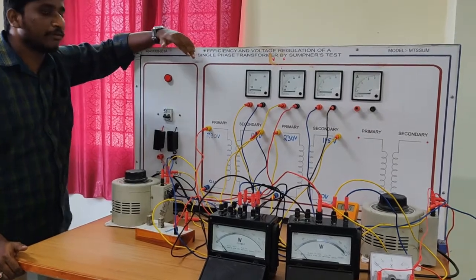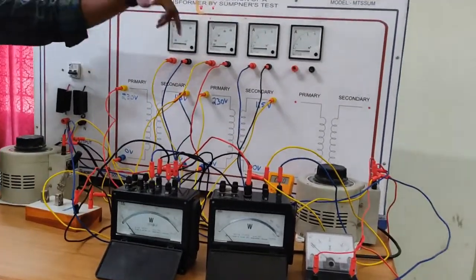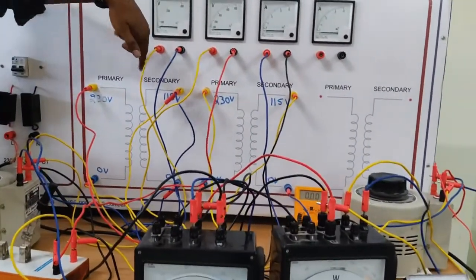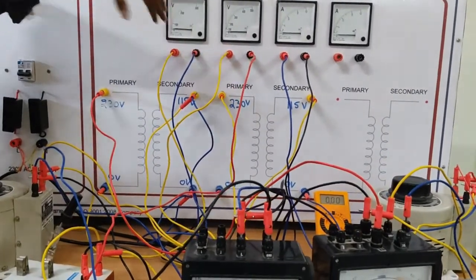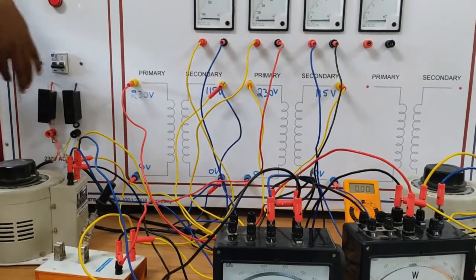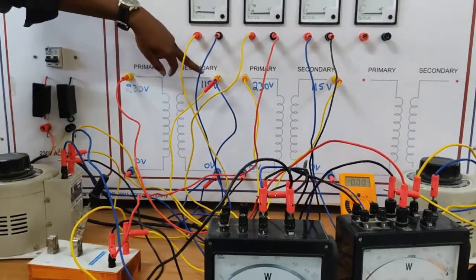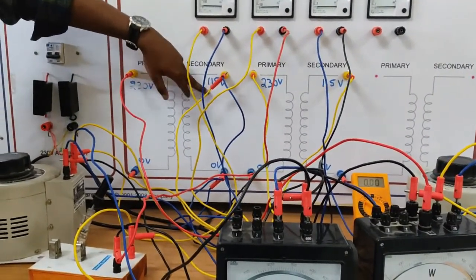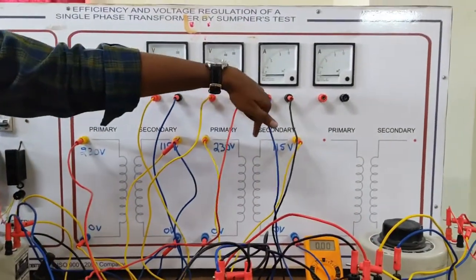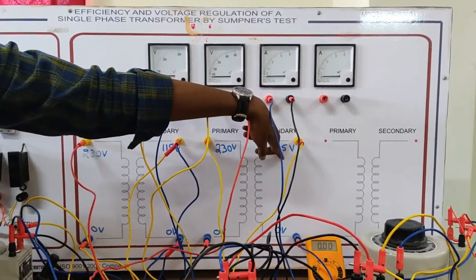Here we have two transformers, 115 by 230 volts: the first transformer and the second transformer. Here I am going to consider 115. In the way we give the connections, the first transformer's 115 volt terminals should be connected in parallel with the second transformer's 115 volt terminals.